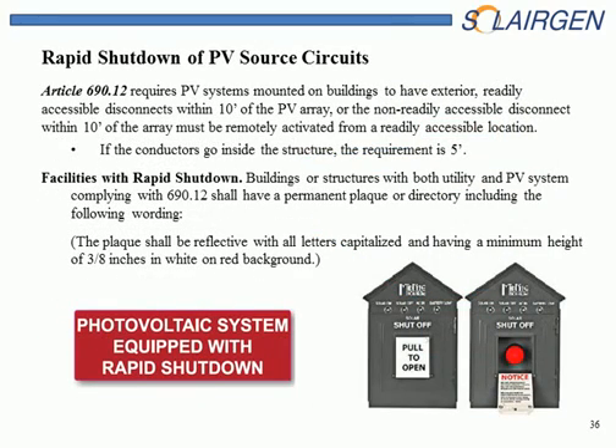The 2014 NEC had a new requirement for rapid shutdown of PV source circuits. This is a great requirement, should have been out a long time ago, and basically it says that if you have DC, high voltage DC coming off the PV array 10 feet away from the PV array on the outside of the building, or 5 feet going into the building, that you have to have a remotely activated disconnect. So this is basically this little mechanism here, which you push that button and it would, in a box, a remotely activated disconnect box, would shut down the PV system or drop it down to no more than 30 volts within these two distance parameters, outside or inside.